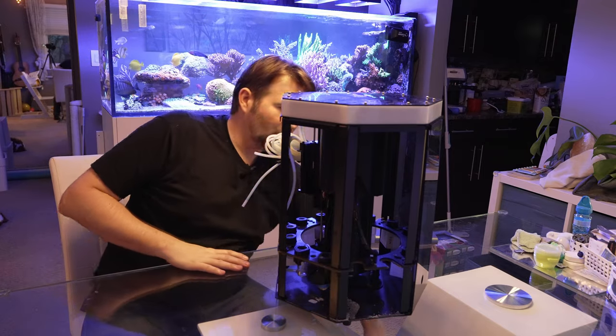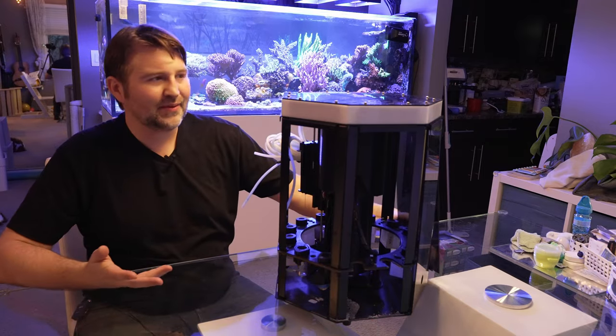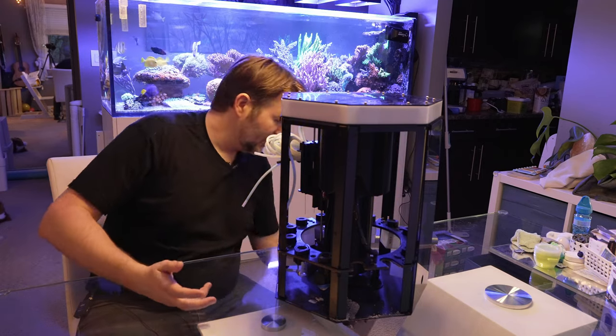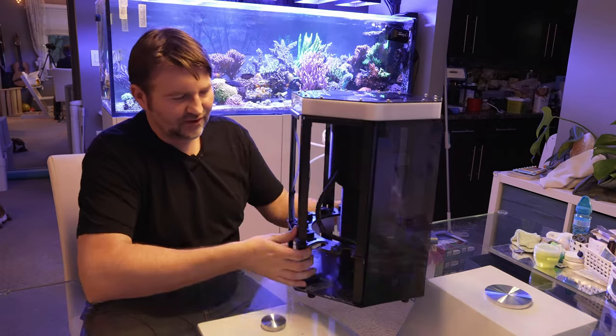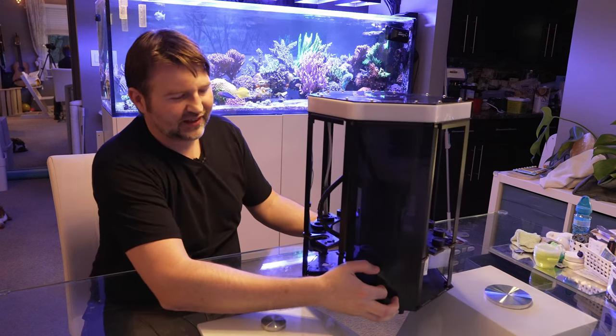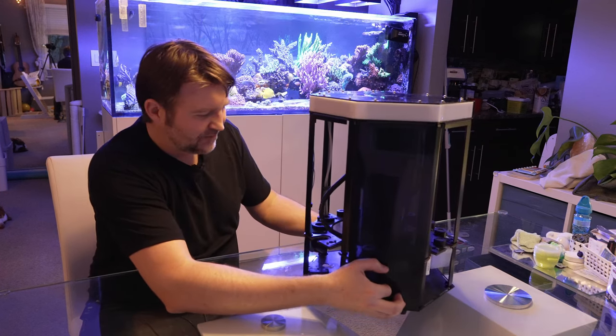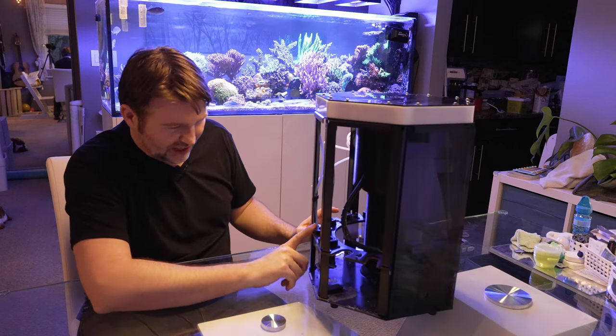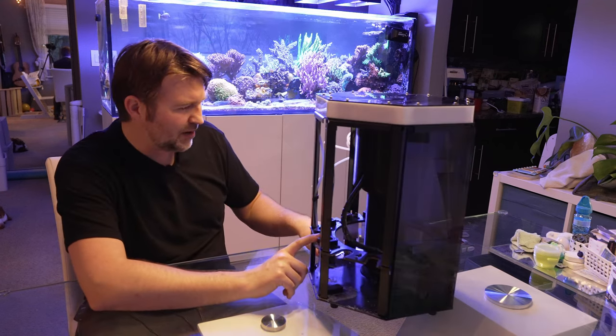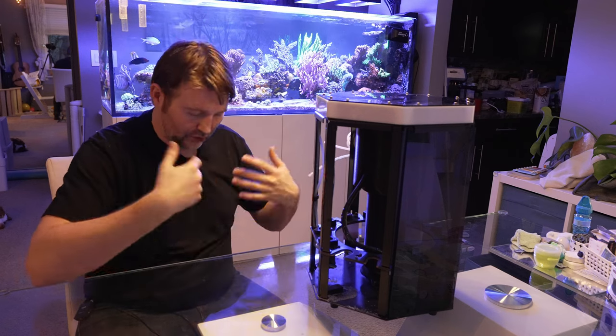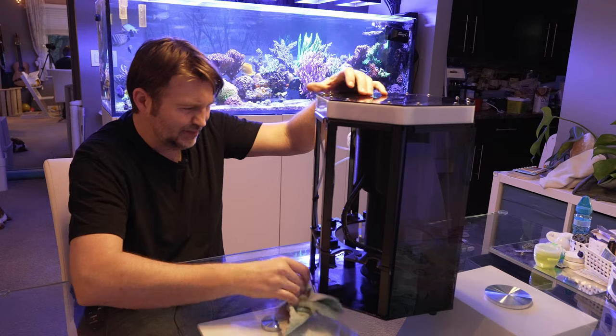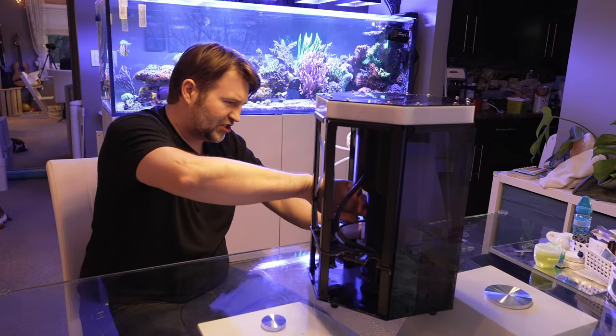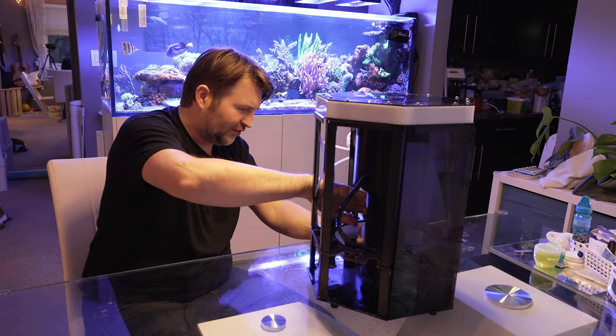So today we're going to be performing some of these upgrades. Now the one thing that does make me happy, I do like to see when companies constantly improve their products. They've added other features where it will stir your reagents more frequently and certain things just to keep them fresher and from going stale. Now with some of these upgrades, they did replace the reaction chamber and I believe the pump head motor they replaced it with a stronger one. So it will mix and test faster, which is pretty awesome. And I'm also going to do a few different maintenance things on this just for good measure like some of the pump heads, just to kind of keep things fresh.